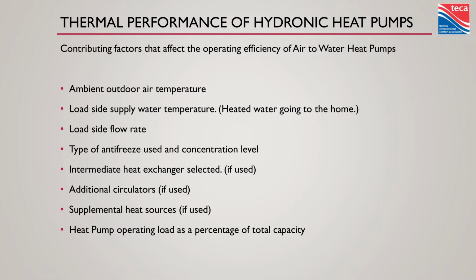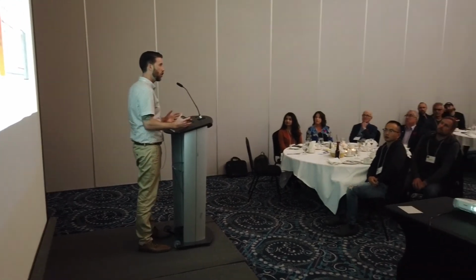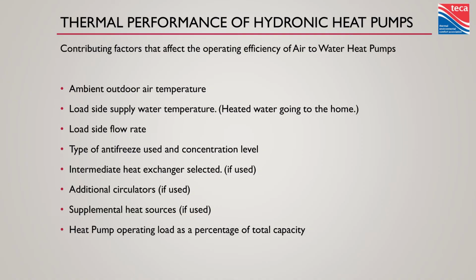Our load side water supply temperature. So the more temperature lift we're trying to get from the heat pump, the harder it has to work, the less efficient, and the less capacity. So what comes out of this, I already see a lot of people doing great low temperature hydronic heat emitter designs because condensing boilers work great at lower return temperatures. That's how we condense those flue gases, another latent heat exchange. But with heat pumps, there's an even more drastic efficiency change with leaving water temperature. And things like adding antifreeze.